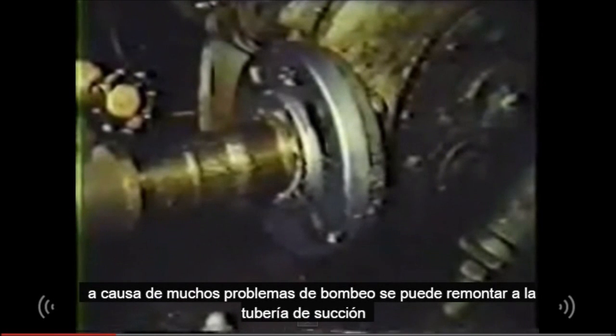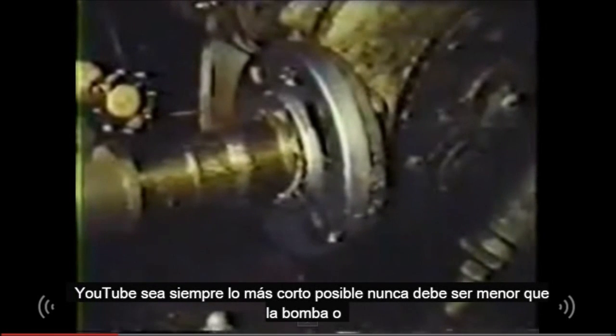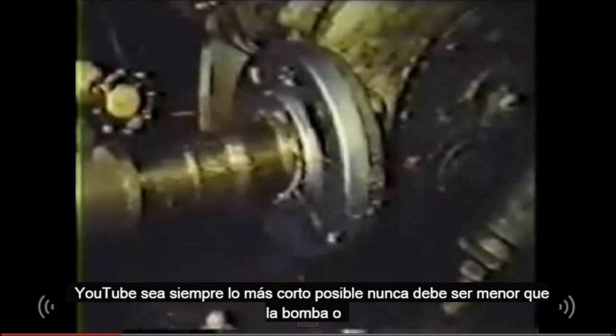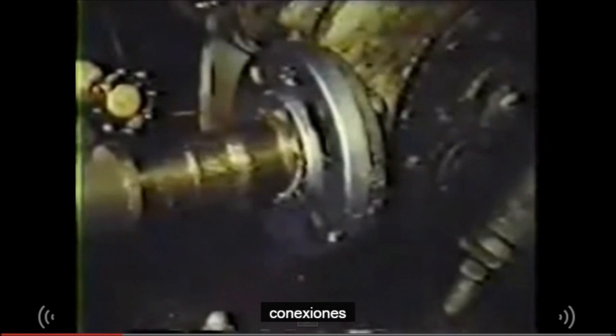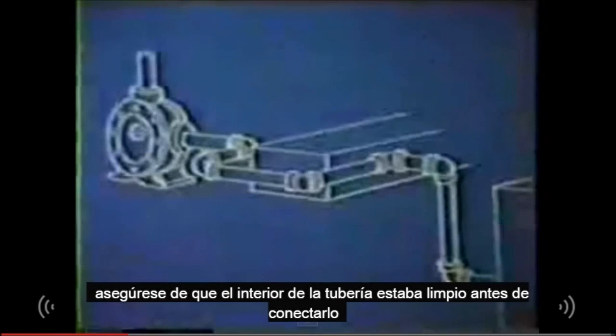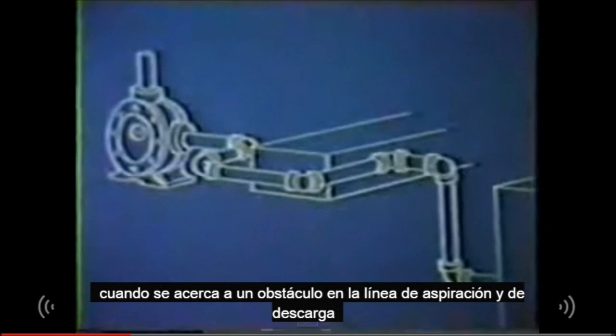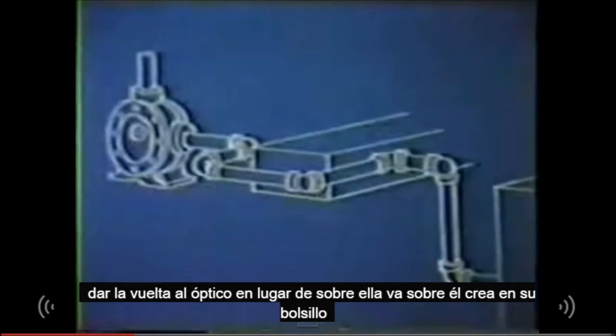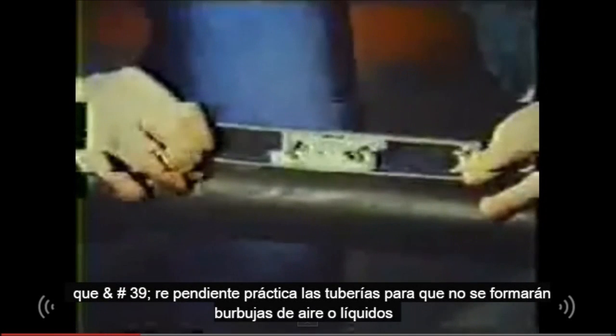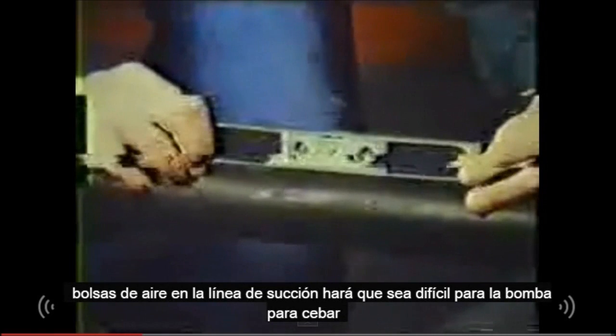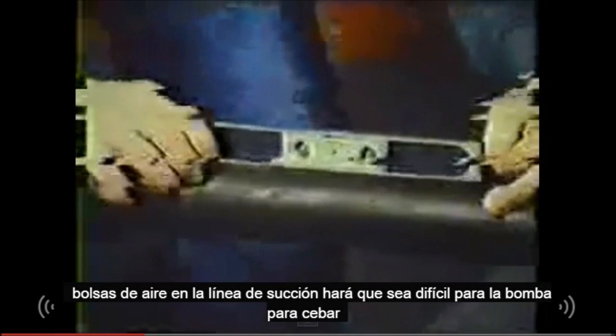The cause of many pumping problems can be traced to the suction piping. It should always be as short as possible and should never be smaller than the pump port connections. Be sure the inside of the pipe is clean before hooking it up. When approaching an obstacle in the suction or discharge line, go around the obstacle instead of over it. Going over it creates an air pocket. Where practical, slope the piping so that no air or liquid pockets will be formed. Air pockets in the suction line will make it hard for the pump to prime.